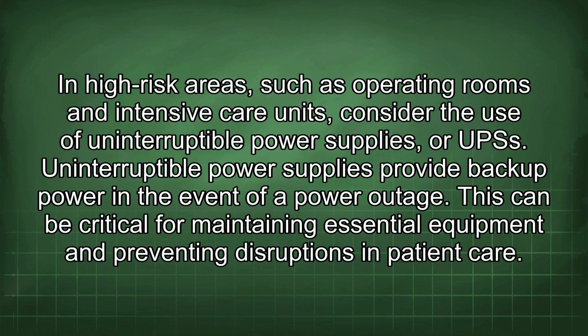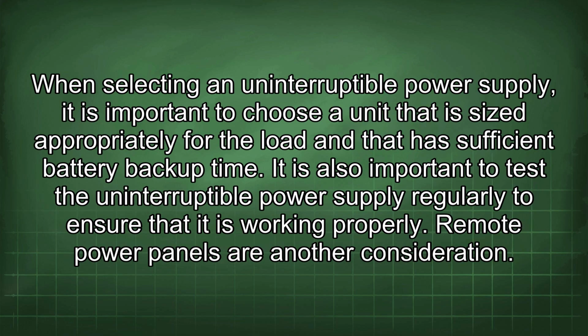In high-risk areas, such as operating rooms and intensive care units, consider the use of uninterruptible power supplies, or UPSs. Uninterruptible power supplies provide backup power in the event of a power outage. This can be critical for maintaining essential equipment and preventing disruptions in patient care. When selecting an uninterruptible power supply, it is important to choose a unit that is sized appropriately for the load and that has sufficient battery backup time. It is also important to test the uninterruptible power supply regularly to ensure that it is working properly.